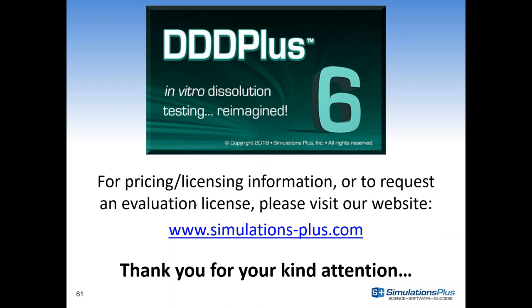A question about the USP-4 flow-through cell and dynamic media change: the media phases are still available in that model, though the options are a little less robust than for the normal USP-1 and USP-2 experiments. You do have the opportunity to change the pHs, and you can use those functionalities with dissolution phases in the USP flow-through experiment.